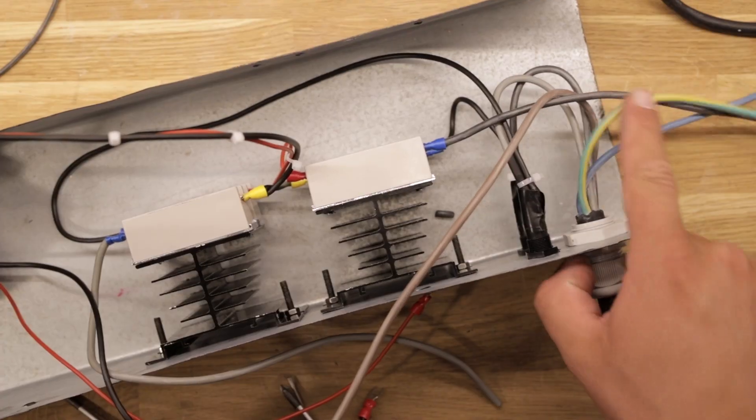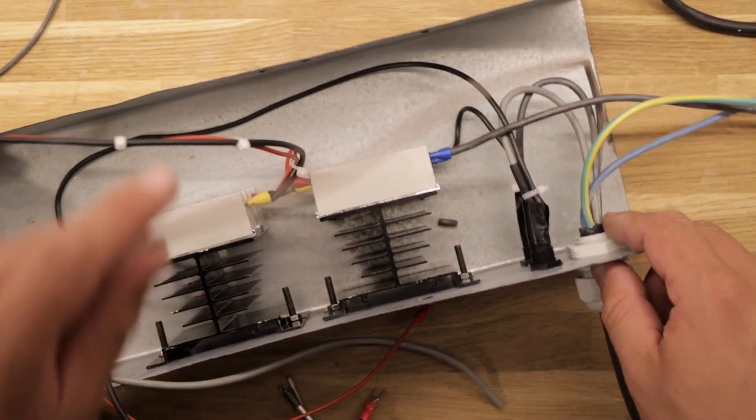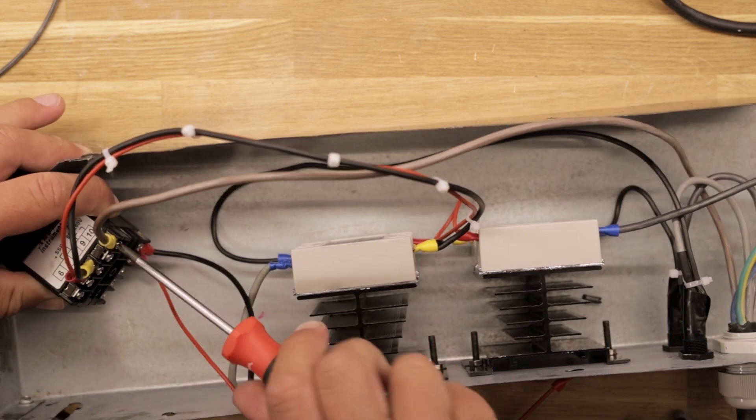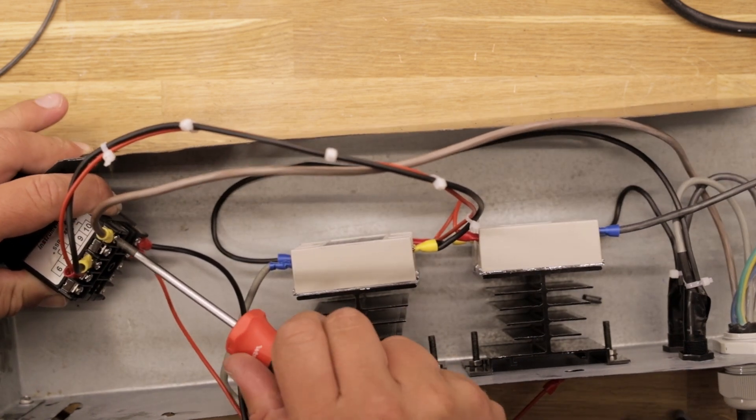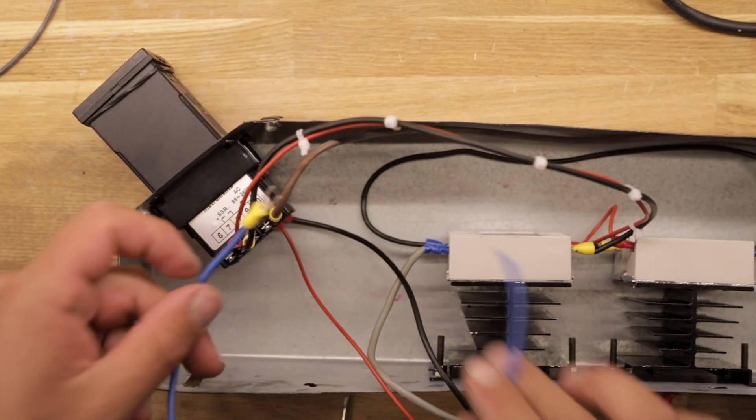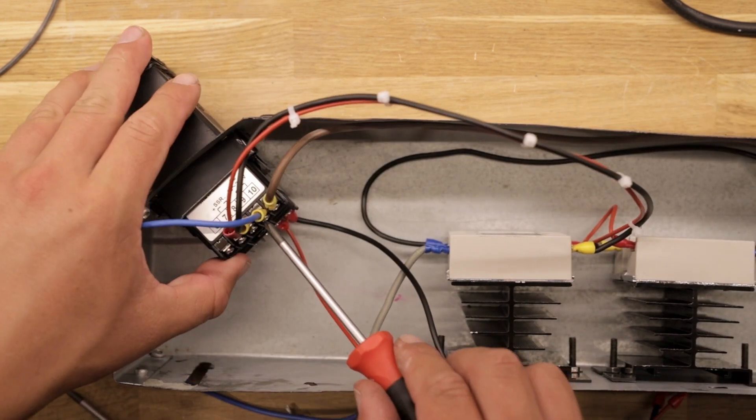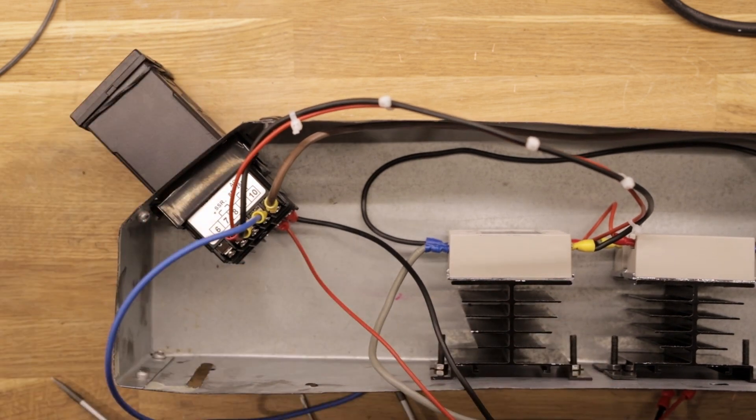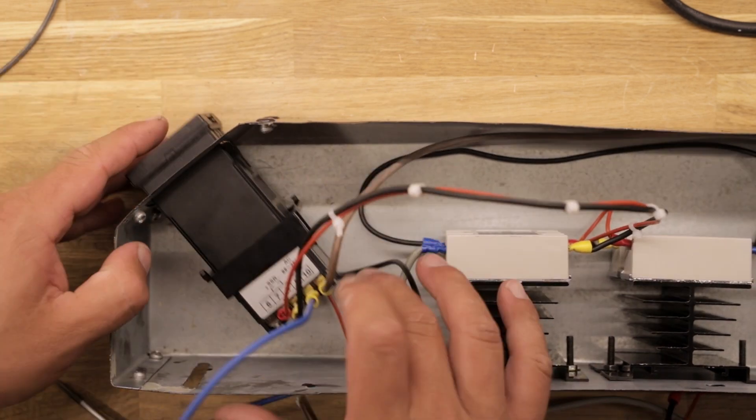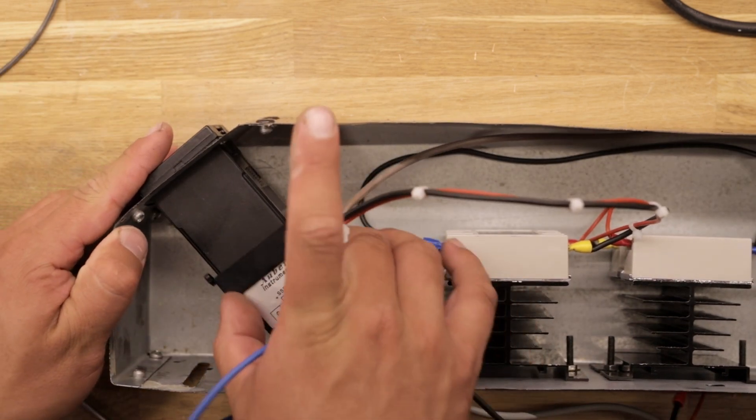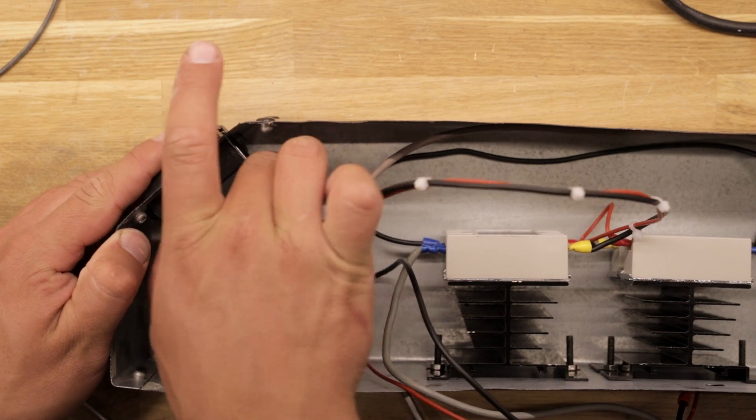Next is the live wire from the power cable, which is connected directly to pin 10 of the PID controller to power it. And then it gets a neutral wire connected to pin 9. The PID is delivered with a smart plastic clip so it can be mounted to the sheet metal box.